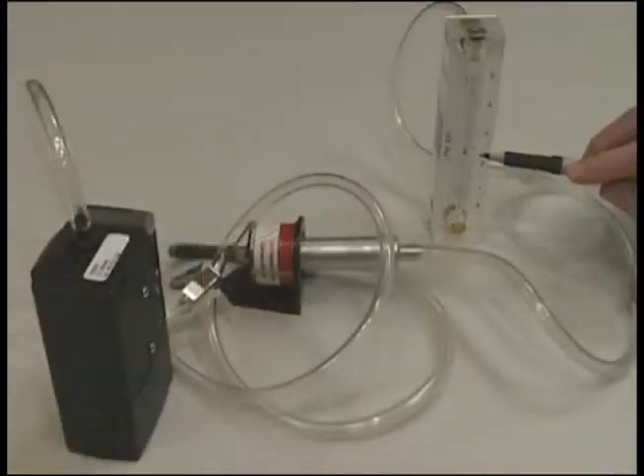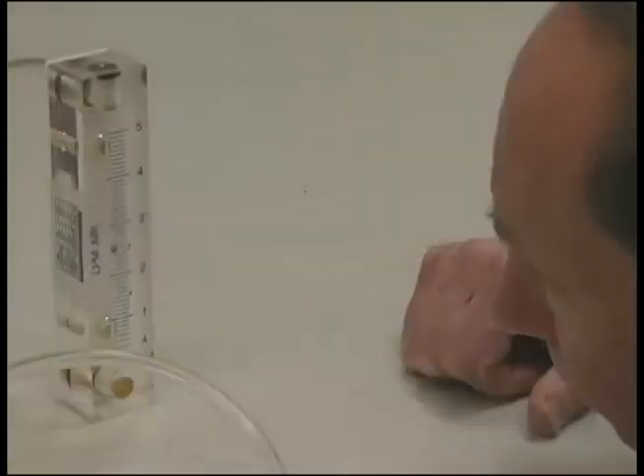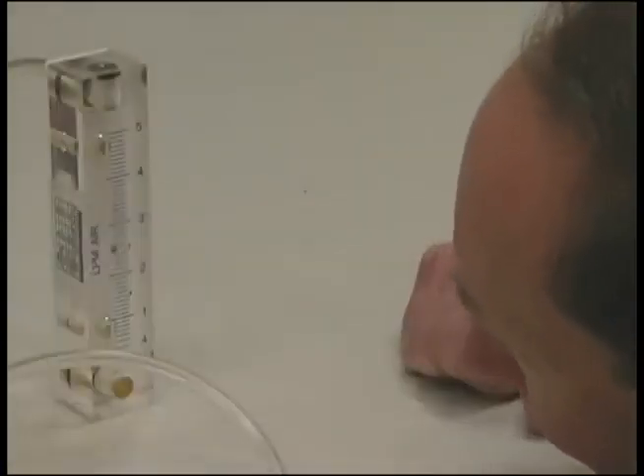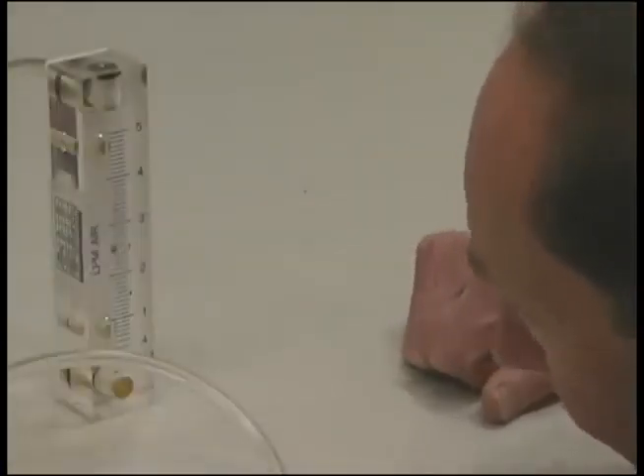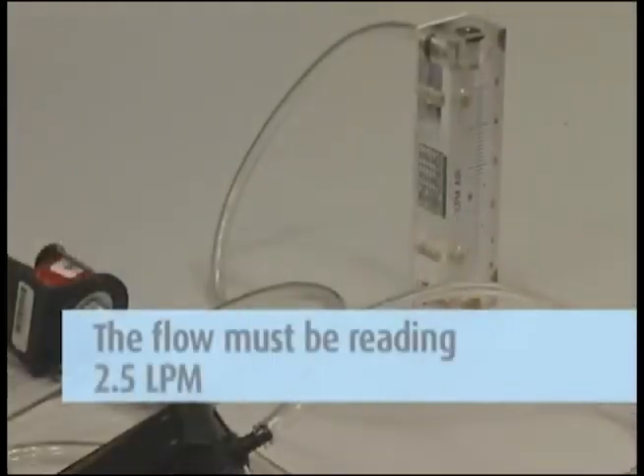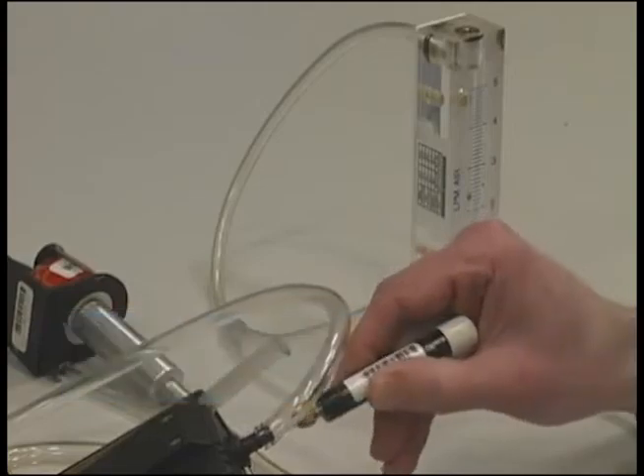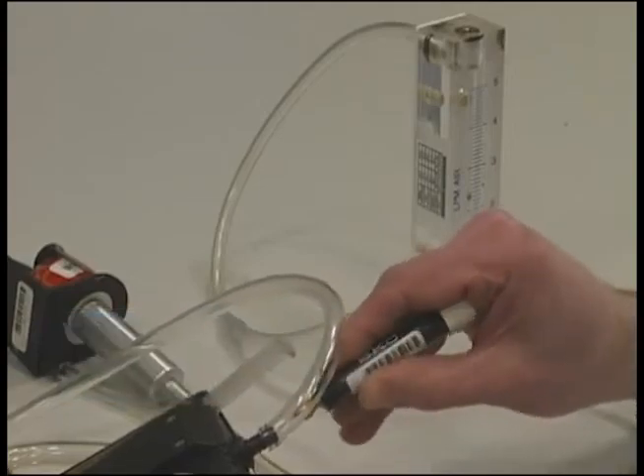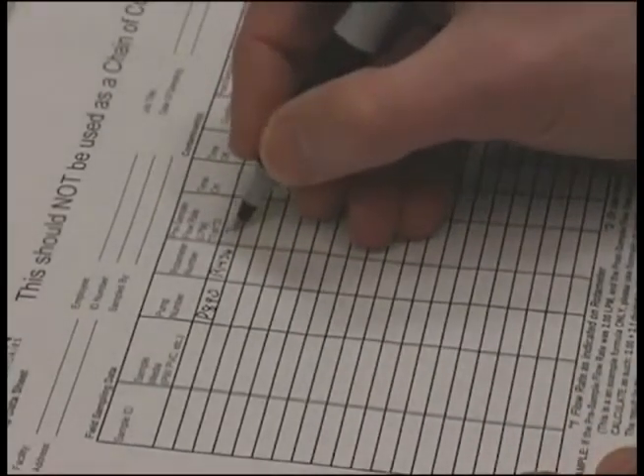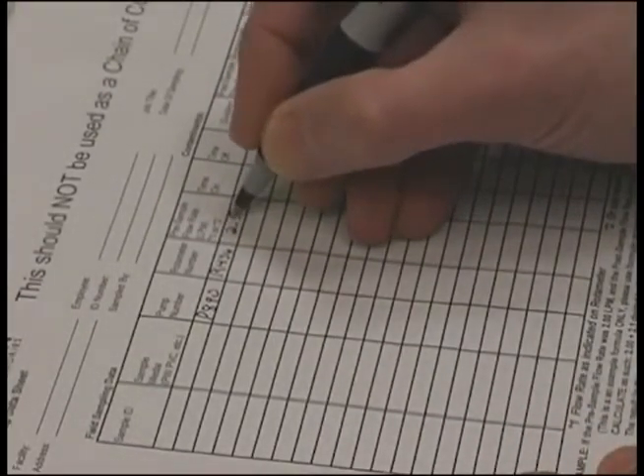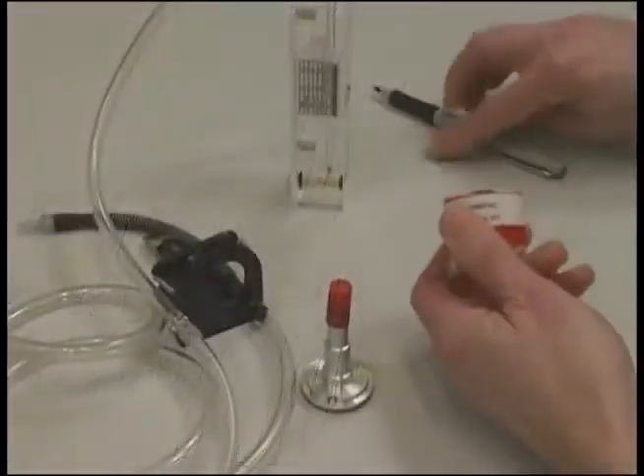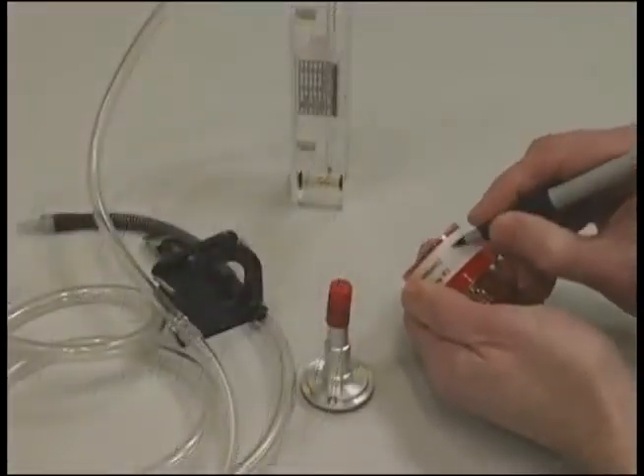With everything sitting on a level, flat surface, check the ball float in the rotometer. Be sure to take your rotometer reading at eye level and use the center of the float for the value. The flow must be reading 2.5 LPM. If you need to adjust the flow, use the set screw on the pump. After you are satisfied with the flow rate, record the value on the field pump data sheet. Remove the calibration cassette and mark it for use in the post-calibration.